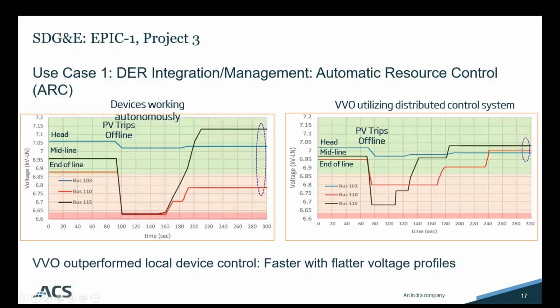Also, this VVO scheme utilized the reactive power, the smart inverter capability of the DER assets to also use the DER as part of the volt-var optimization scheme. So that helps fine tune beyond just the traditional devices of regulators, LTCs, and capacitors. Those inverters also contribute to being able to flatten this voltage profile.